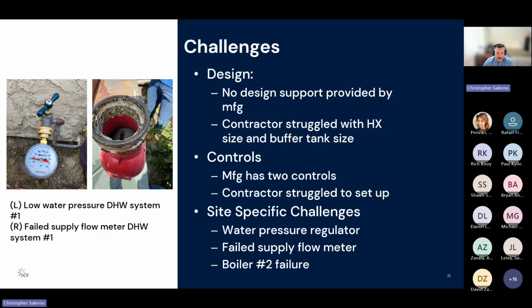So also they struggled with doing a proper buffer tank size. Initially they didn't know exactly if they needed a buffer tank or not, and how much is sufficient, in finding and sourcing a reasonable, low-cost tank for that purpose, if it were only 20 or 30 gallons that would be needed. Fortunately, here we needed at least 80 to 100 gallons, so we used an 80-gallon tank.